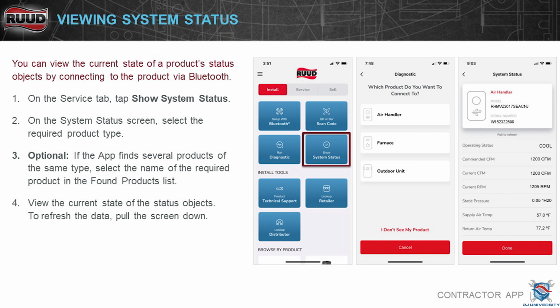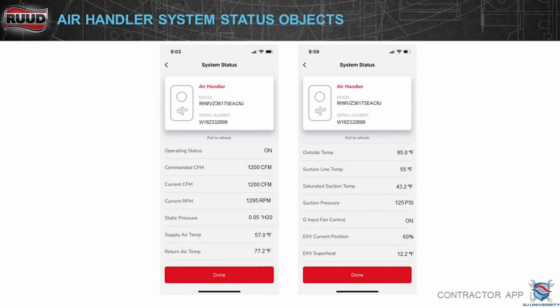You also can look at supply and return air temperatures. On the outdoor unit, it's going to give you outdoor temperature and suction line temperature, which is read on the outdoor unit. There's a thermistor on the suction line as it enters the unit, and that's where it's actually reading it. It's not reading it on the indoor EEV. And the reason they did that is because not all units have EEVs, some of them have TXVs, so they put it on the outdoor unit.